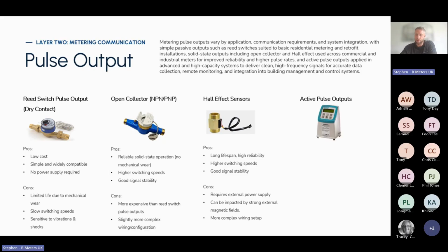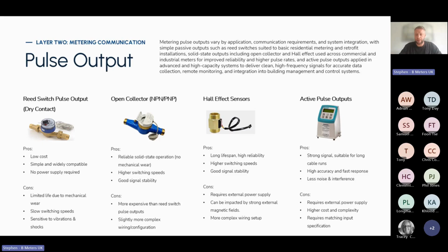And lastly, active pulse outputs, which you'd likely find on the Siemens MagFlow meters, for example. And these are best in class. They're strong signal, suitable for long cable runs, high accuracy, fast response, less noise and interference. The downside is it requires external power supply, higher cost for sure, and complexity. And you need something that can pick up an active pulse output, whereas open collector and reed switch pulse outputs are just much more commonly used. For mechanical meters, active pulse outputs just wouldn't ever be a solution, whereas obviously open collector has found a place in the market.